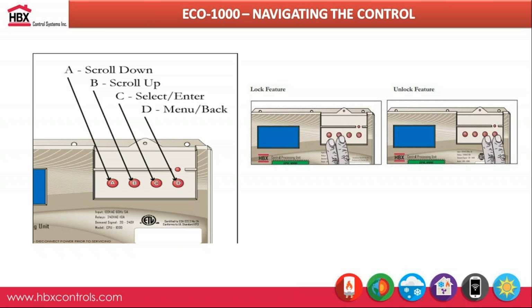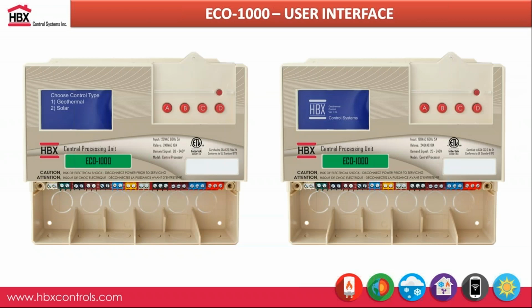We do have a lockout feature on the Eco 1000, so if you hold down the A and B buttons for 10 seconds, it'll put that controller into lock. So once you've set up the controller, and you don't want anyone messing around with the settings or anything, you have that option. To unlock it, you simply hold down the C and D buttons this time for 10 seconds, and that unlocks the controller on the 1000.